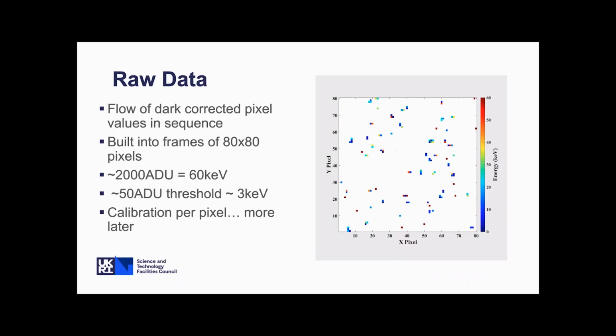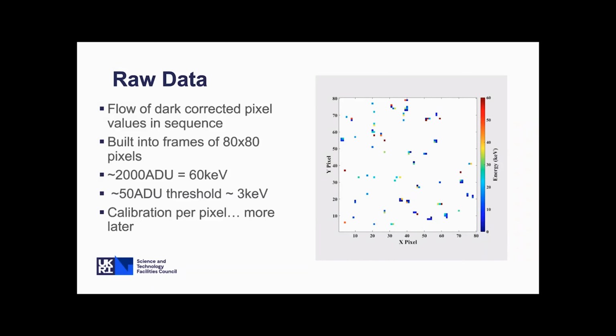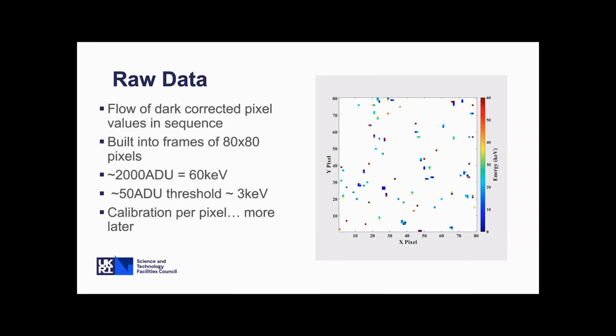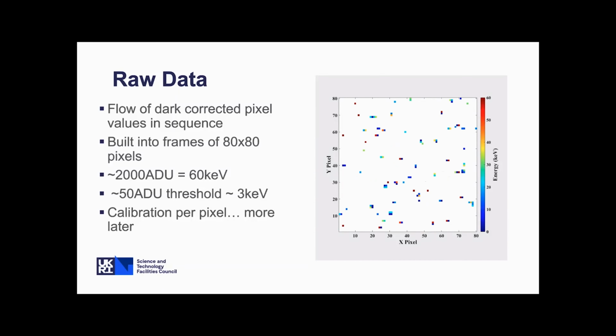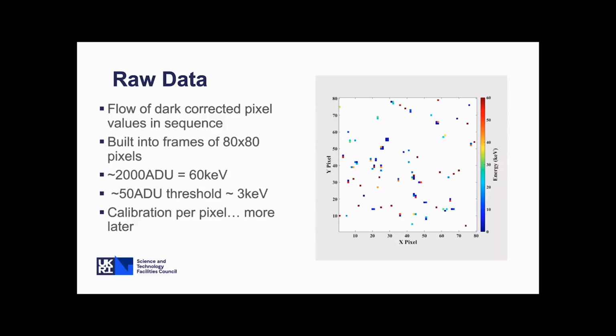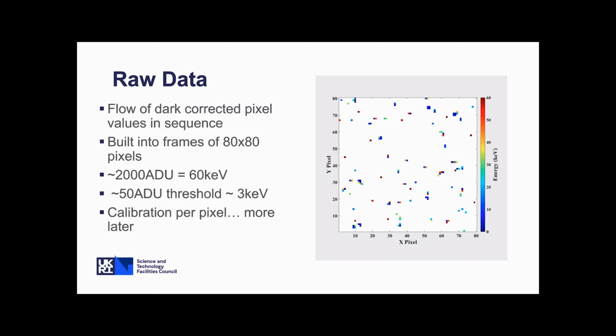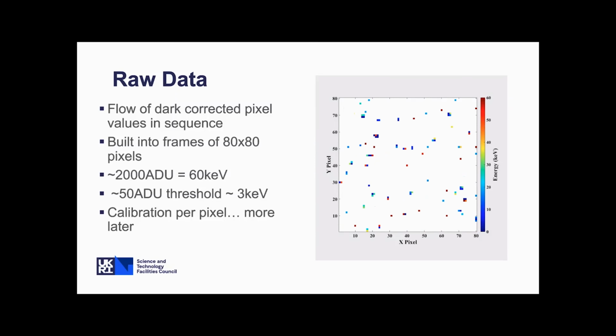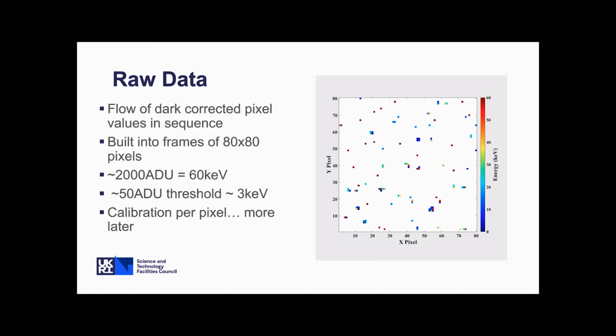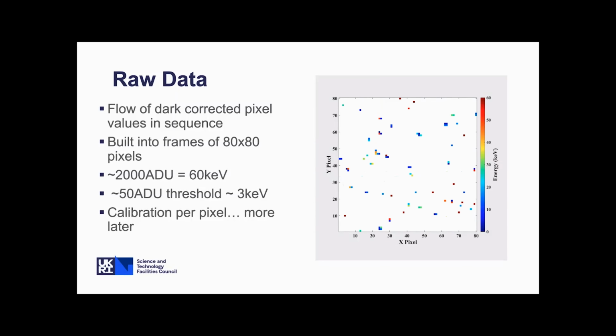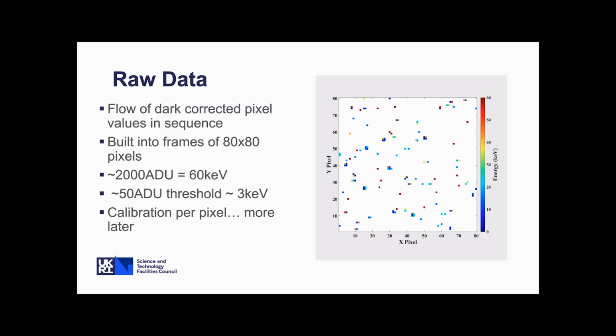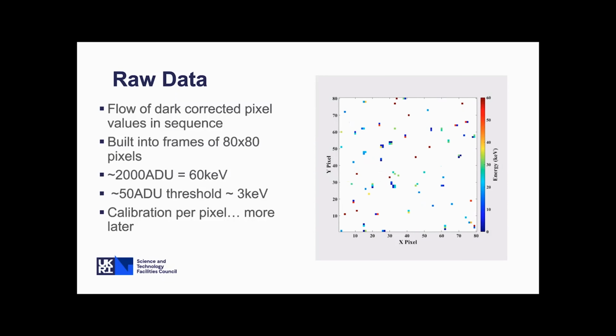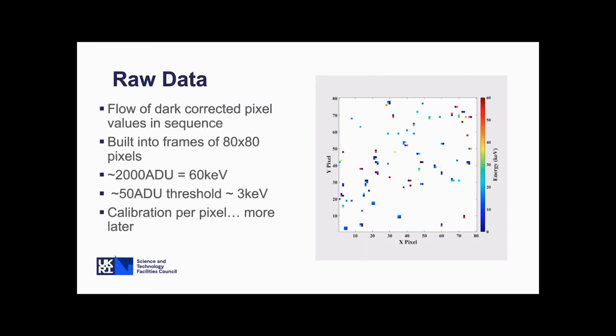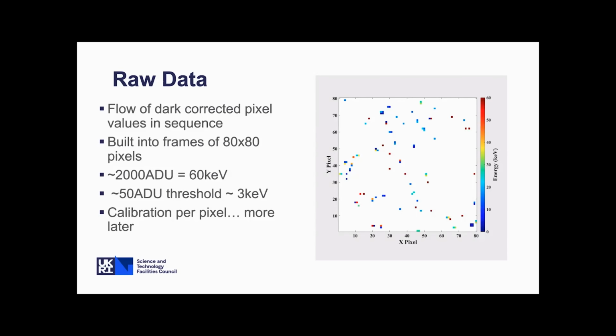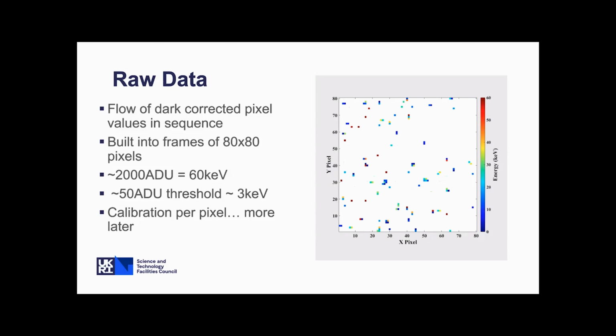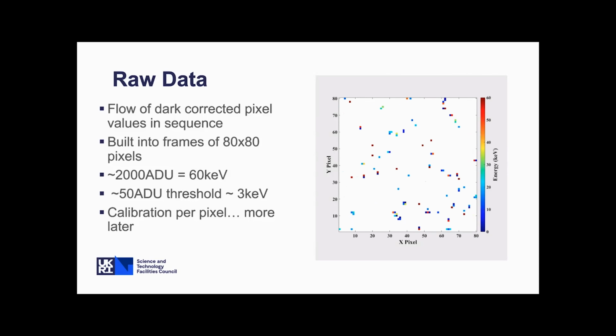So the frames are 80 by 80 pixels, which matches the size of the array. Some rules of thumb are that the raw data gives an output of about 2000 ADU, which is equivalent to 60 keV, which is always a useful number to remember. The low energy threshold we typically operate at is about 50 ADU, which is equivalent to 3 keV. And that raw data can be used then to generate calibration coefficients, which would come with the detector. And we'll go into that in a bit more detail later.